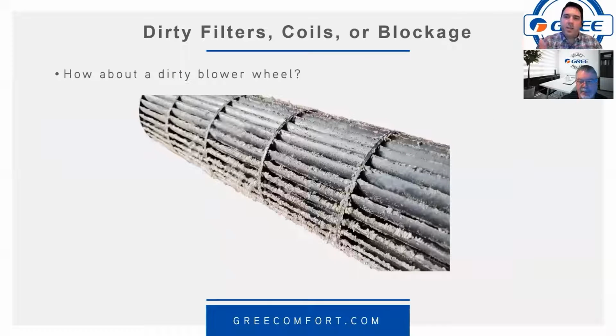How about a dirty blower wheel? A quick check, Keith, real quick. You're mentioning reset the system, pull the main power for 5 to 10 minutes. If it does clear the code, then it's likely something else besides a failed pressure switch. Right. And we're going to talk about it a little more, but the system will try to adjust. Its desire is to keep running. So it's going to slow down, and when it sees some of those conditions, it has logic in there to try and keep it running as long as possible.